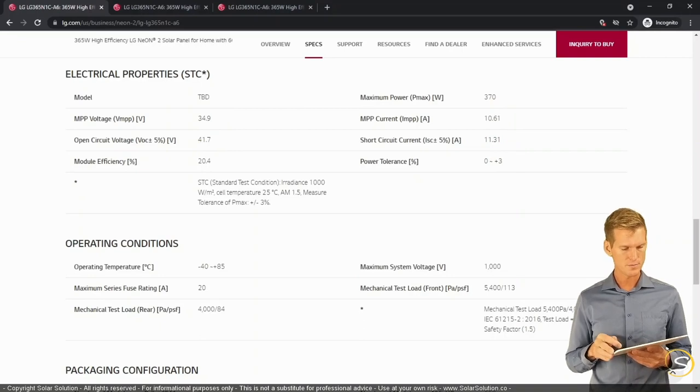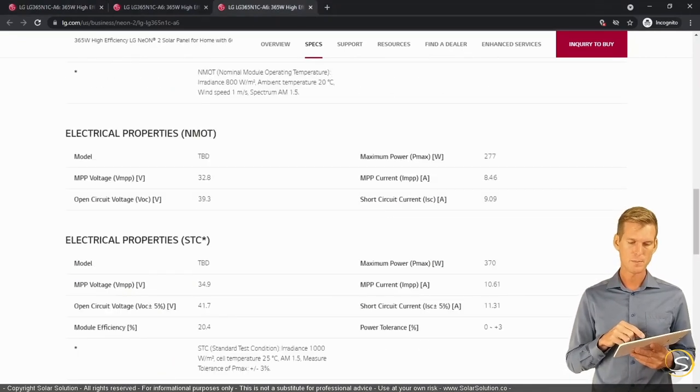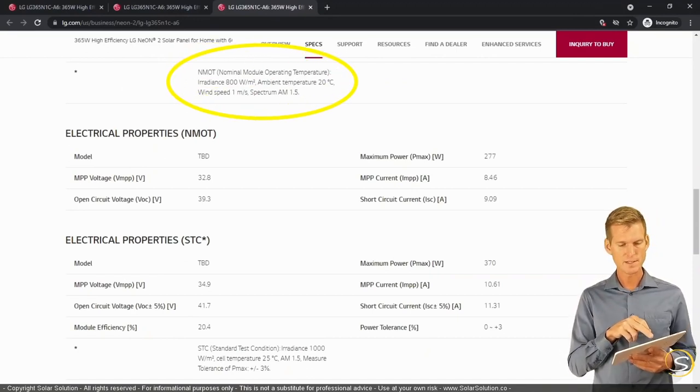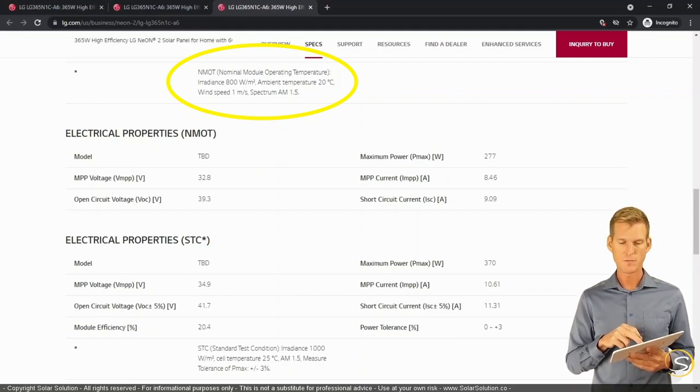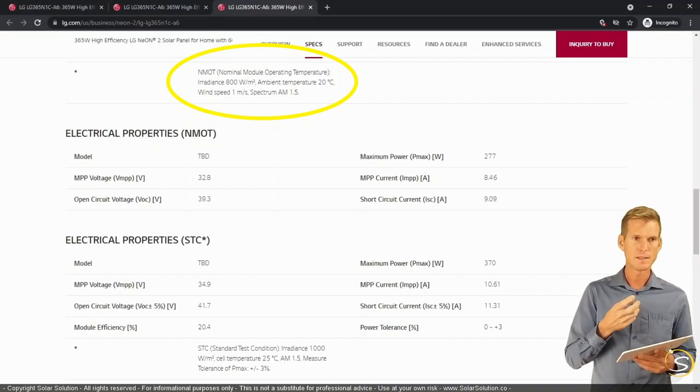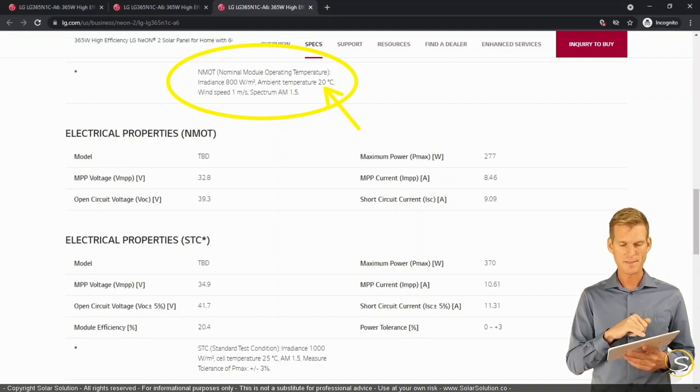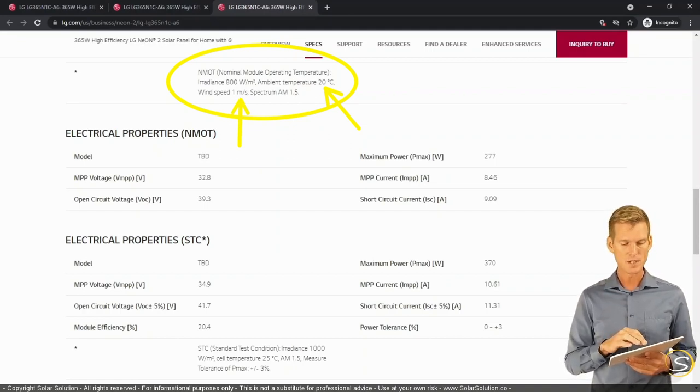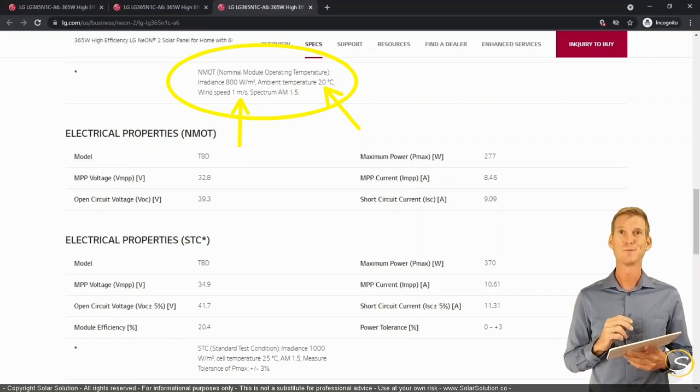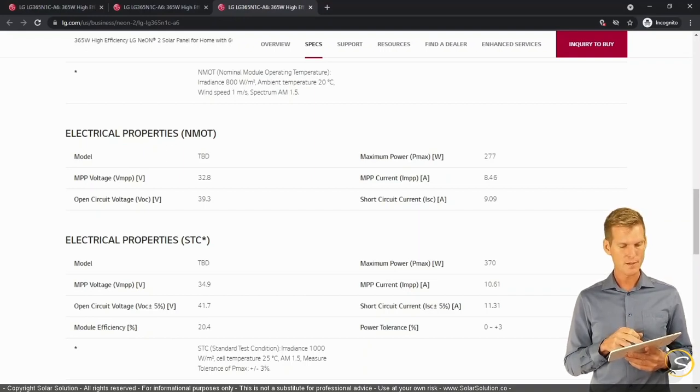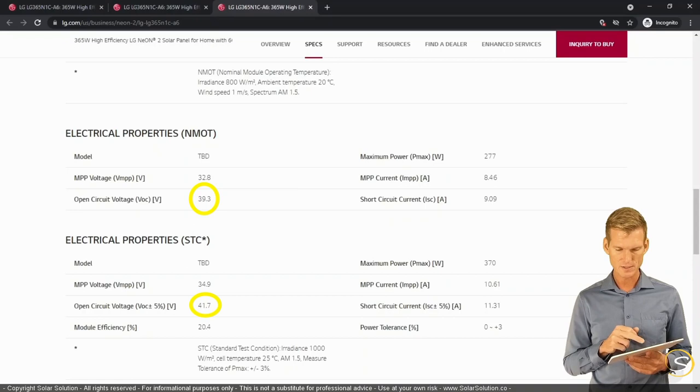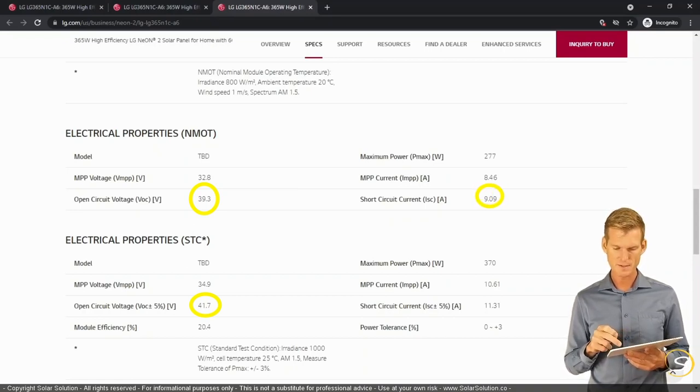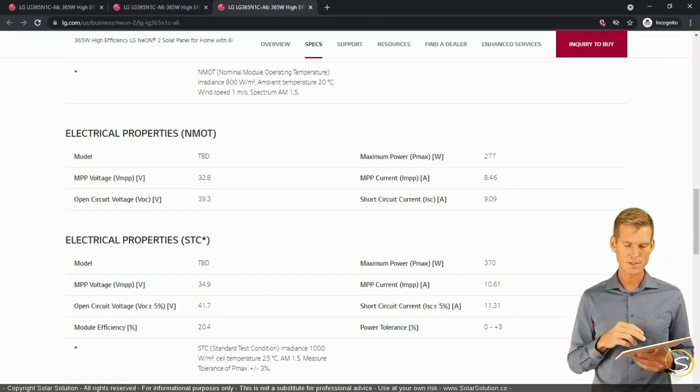Now there's another value that you might come across as well, which is called the NMOT, the Nominal Module Operating Temperature. So it's just a different set of test conditions. So here you can see that for testing the same panel, they've used a lower irradiance setting of 800 watts per square meters. And instead of keeping the cell temperature steady, what they're doing is they keep the ambient temperature steady and then the amount of wind speed steady, so ambient temperature is 20 degrees Celsius or 68 degrees Fahrenheit, and the wind speed is one meter per second, which is really, really low. You can barely feel one meter per second. So you can see that under these test conditions, we have a lower open circuit voltage, 39.3 versus 41.7 under STC test conditions. And the short circuit current is 9.09 versus 11.3, which makes sense, because under NMOT, the irradiance level is lower. Instead of 1000, it's 800 watts per square meters.